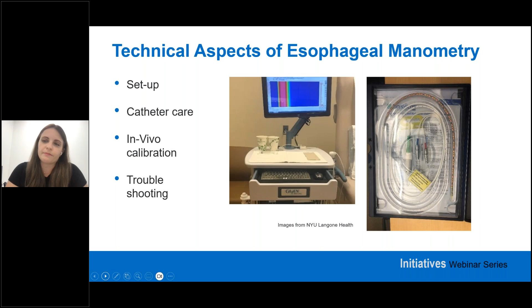I mentioned in vivo calibration on this slide. This is essentially a function that's recommended to be performed weekly so that the catheters can recognize a typical human body temperature to allow for thermal compensations that are picked up by the catheter while it is in the body. The Medtronic ManoScan software actually does automatically apply this reading when the catheter is removed from the patient, so it's not exactly required anymore. This used to not be something that the software included, but it is important to still perform in vivo calibration weekly in case this function is not working for whatever reason. It can be a little cumbersome, but again, it is still important and recommended.